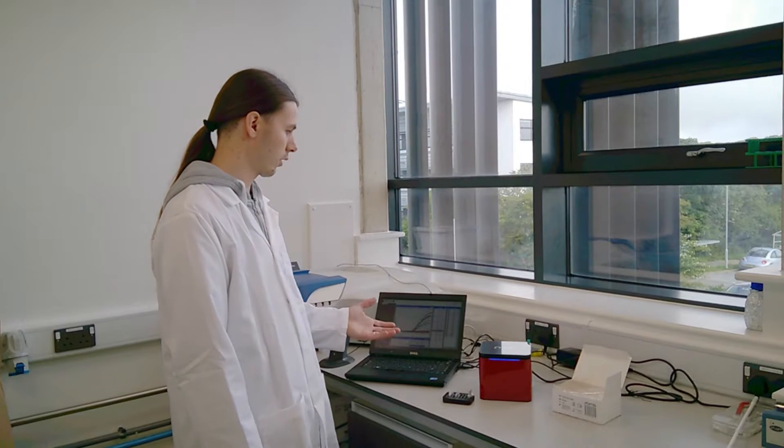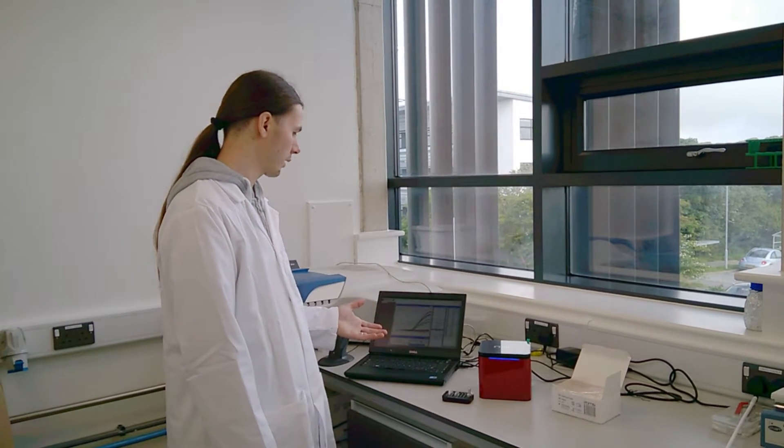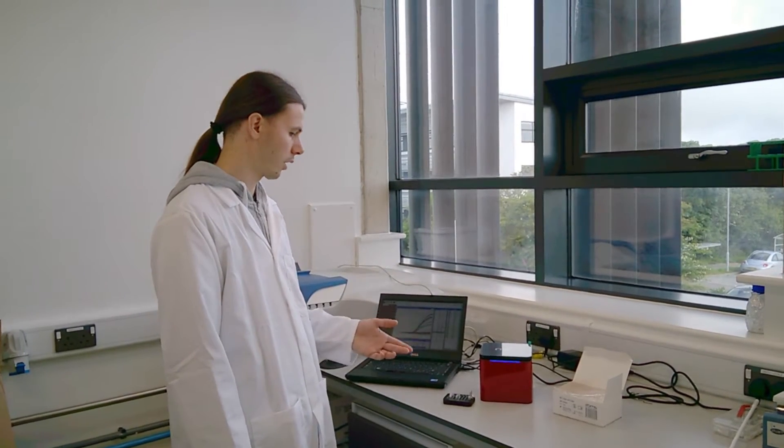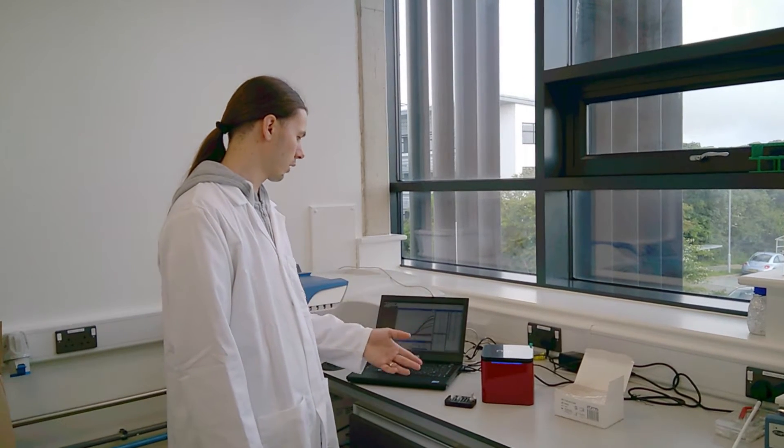The software is quite intuitive. It's not patronizing at all. Some software requires you to specify the assay beforehand before you can run. Here you can set up your tubes, insert, and run it.